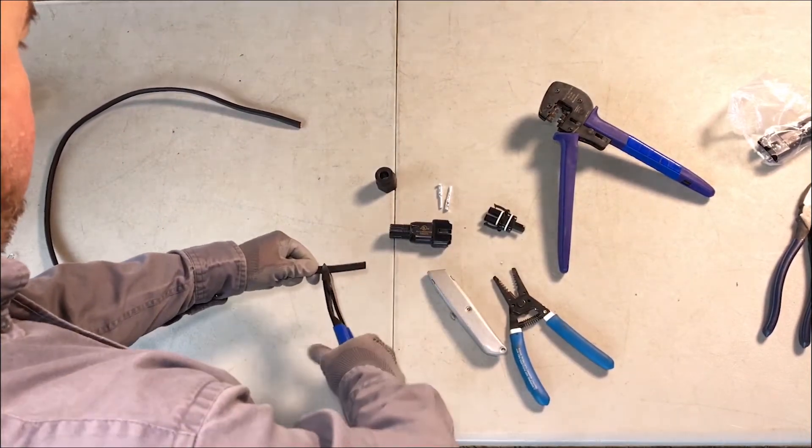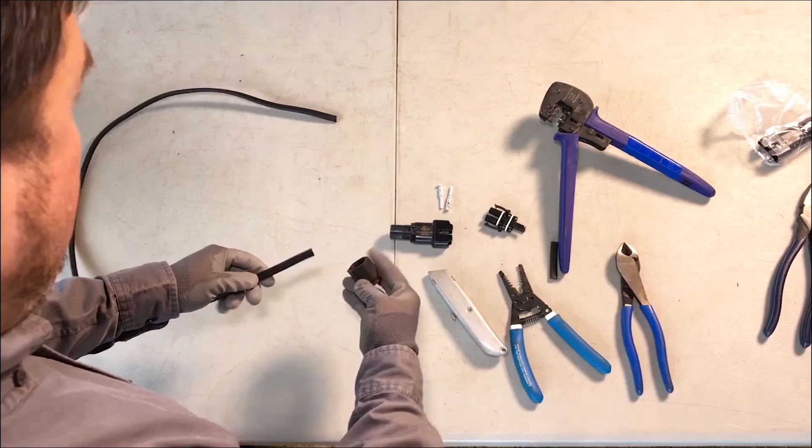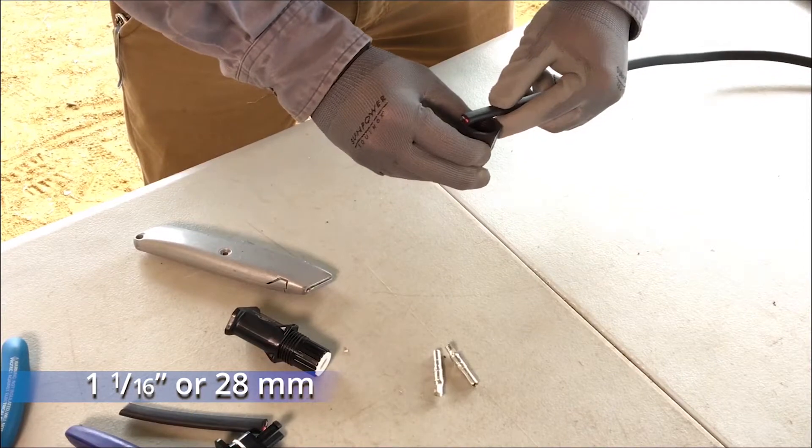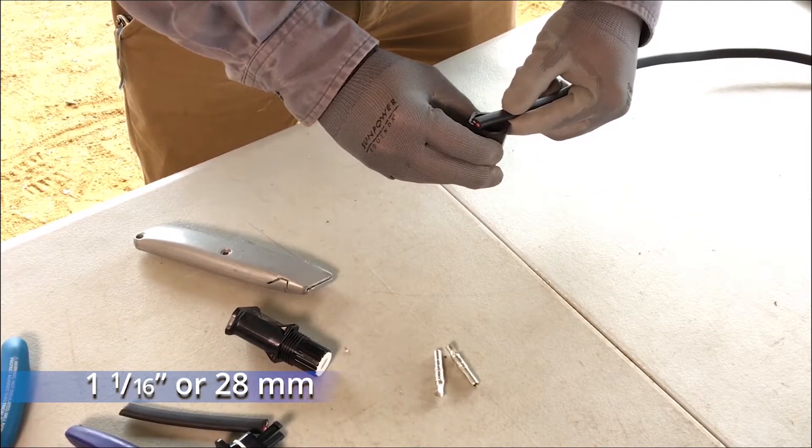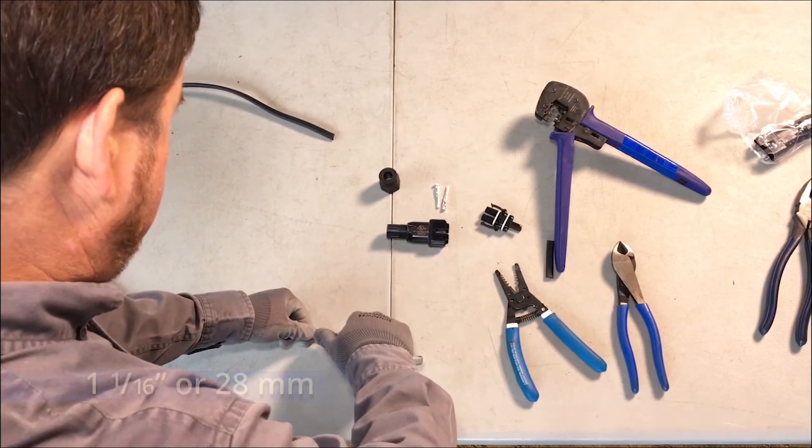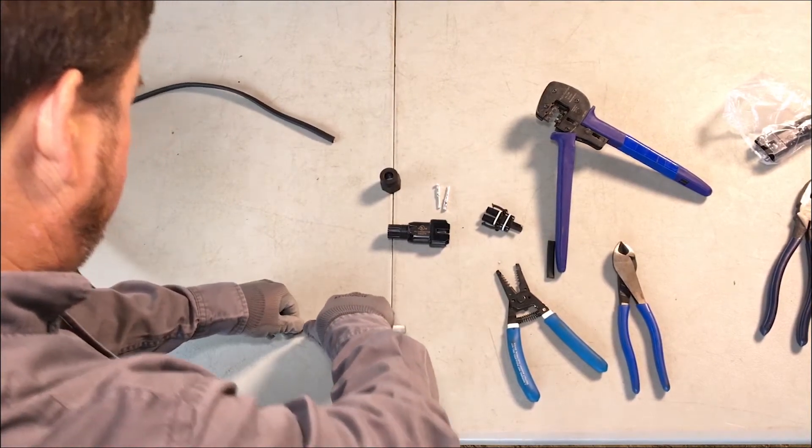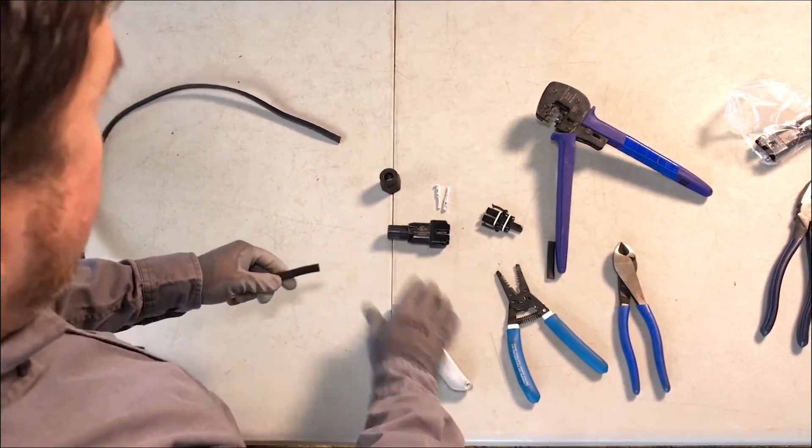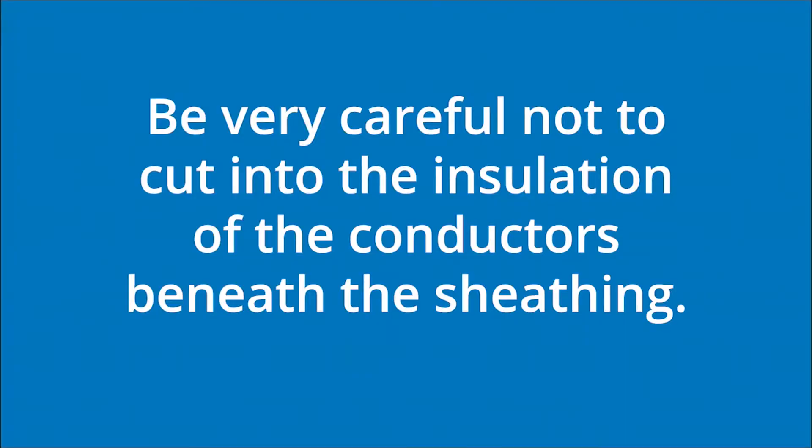The connector nut width doubles as a jig for how much wire to strip from the outer trunk cable. Measure with the nut and then use the razor knife to strip 1 and 1/16th of an inch of the black outer jacket from the cut end of the cable in order to expose the black and red conductor insulation. Be very careful not to cut into the insulation of the conductors beneath the sheathing.